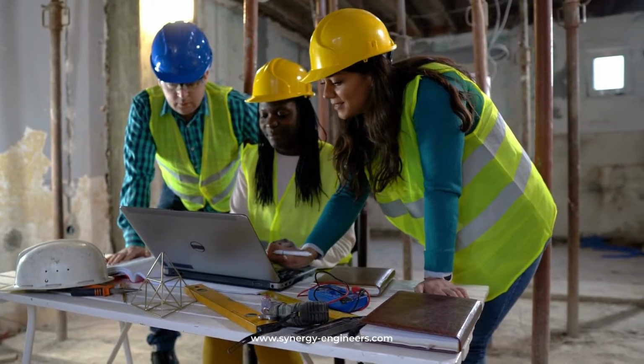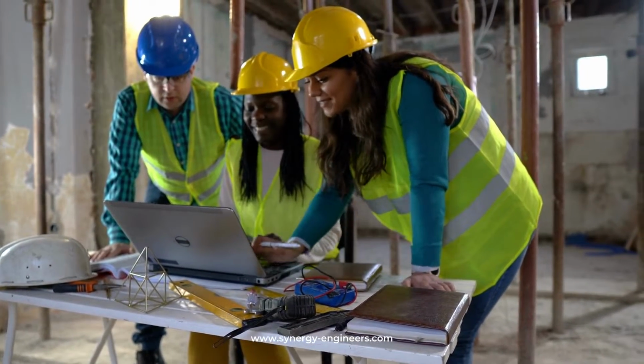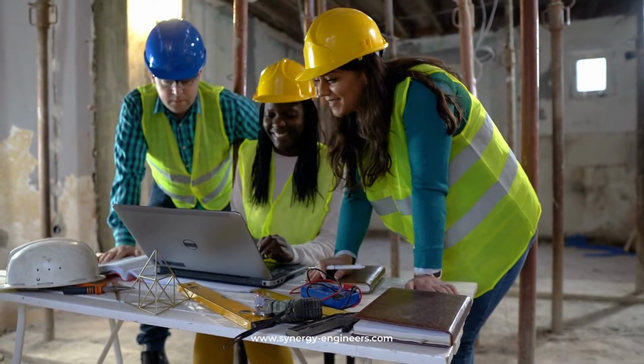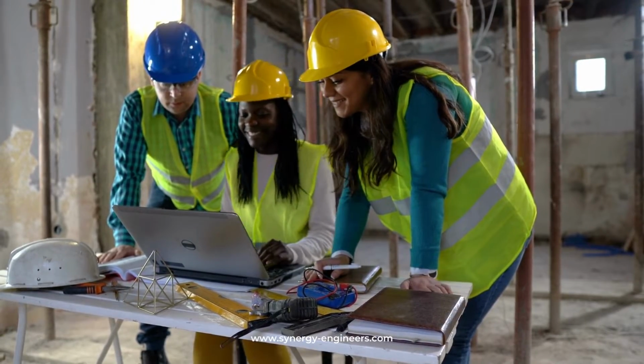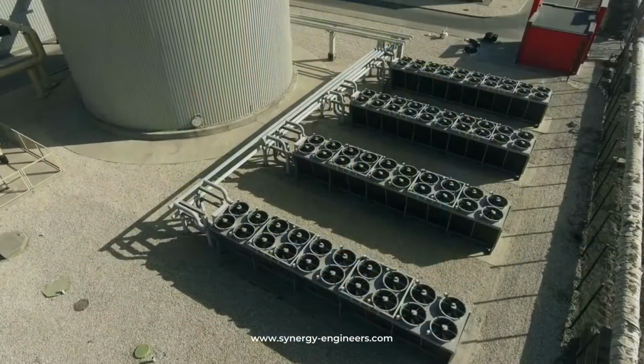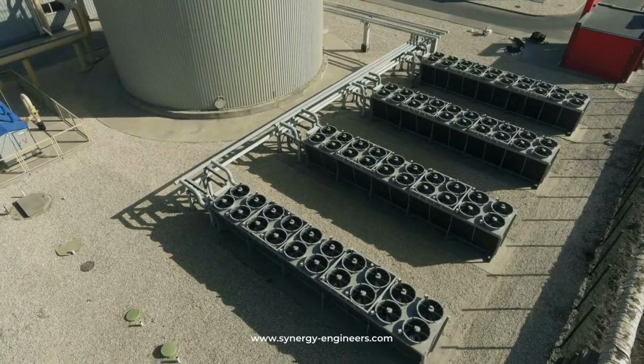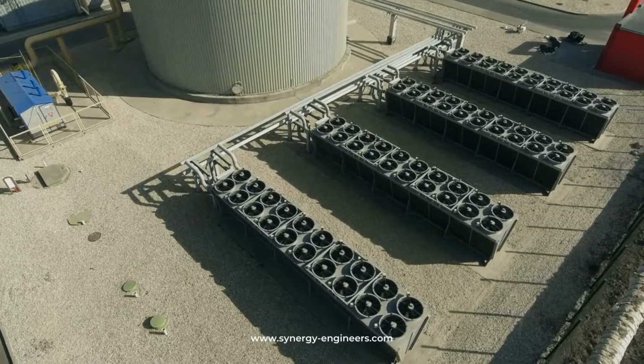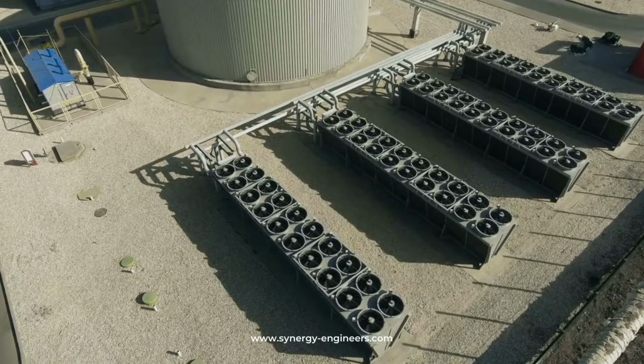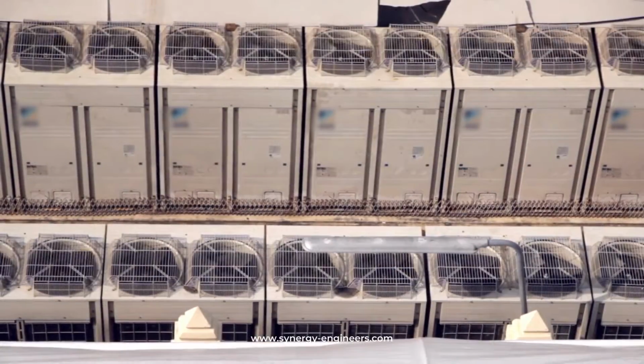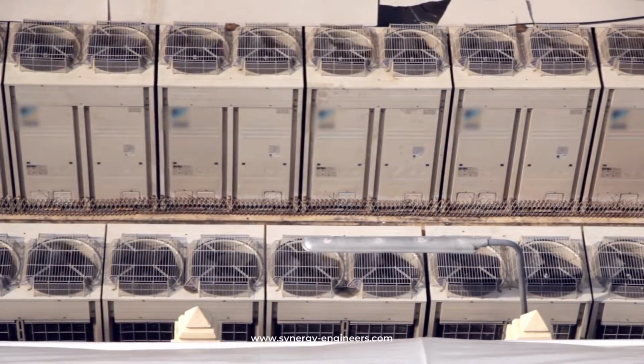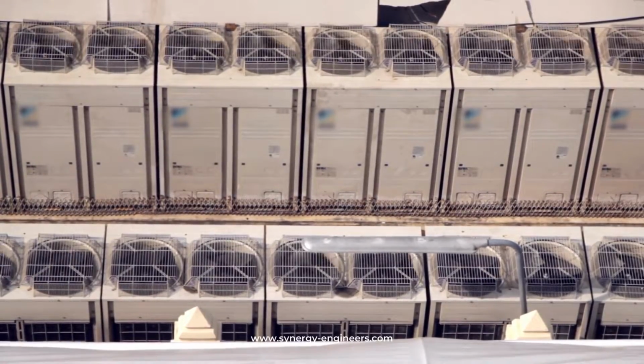but what we're really looking at is not putting a VFD on each individual fan itself. We're putting a VFD controller on the array as a whole. So as one fan drops off, or as system characteristics change downstream of that air handling unit, based on the programming and the sequencing, that drive is going to control the fans in a different way. It's going to speed them up at certain percentages and things like that.